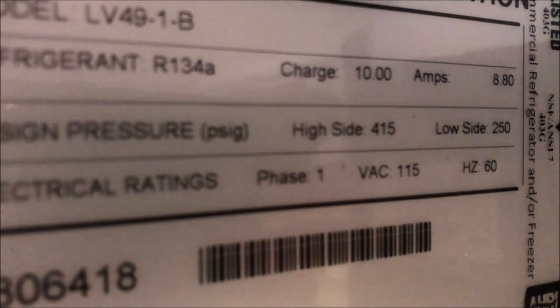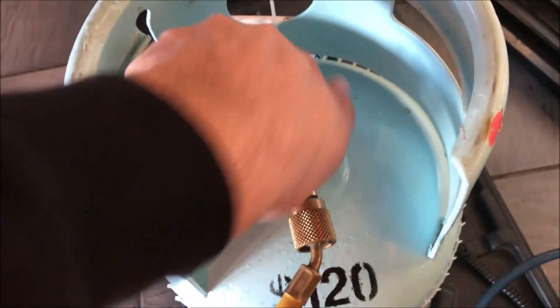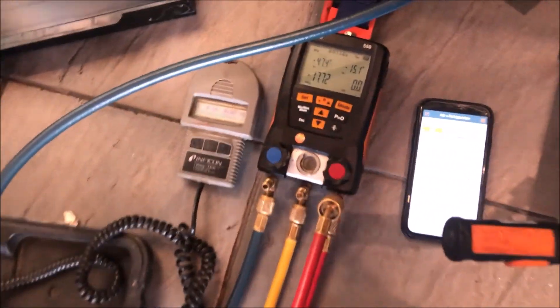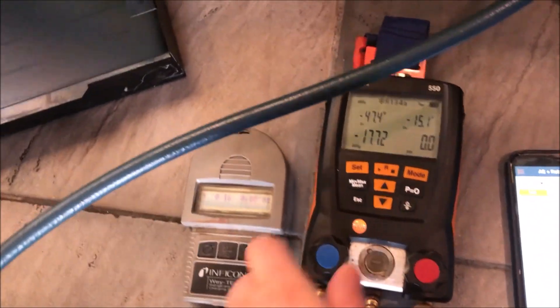So let's go determine if we're low on charge or we have a restriction. How we're going to do that is we're going to add in the charge and let's see if our pressures change. Let's go to our data plate here. You can see our charge here is 10 ounces R134a. So let's just start adding in a little bit of refrigerant and see what happens to our pressures.